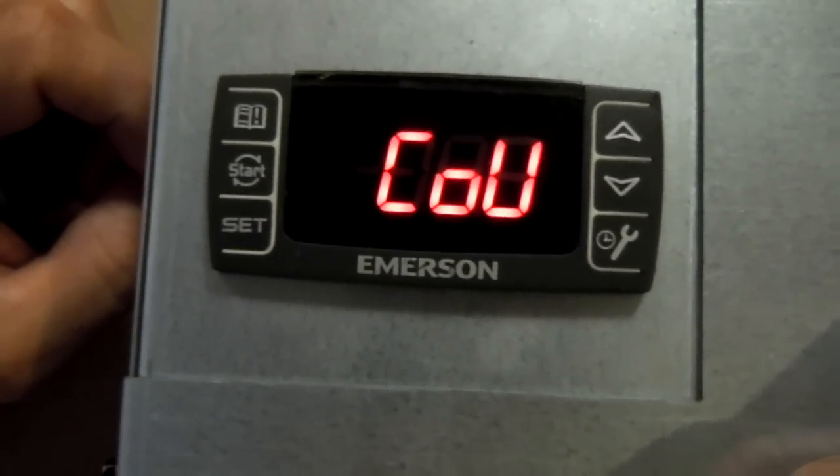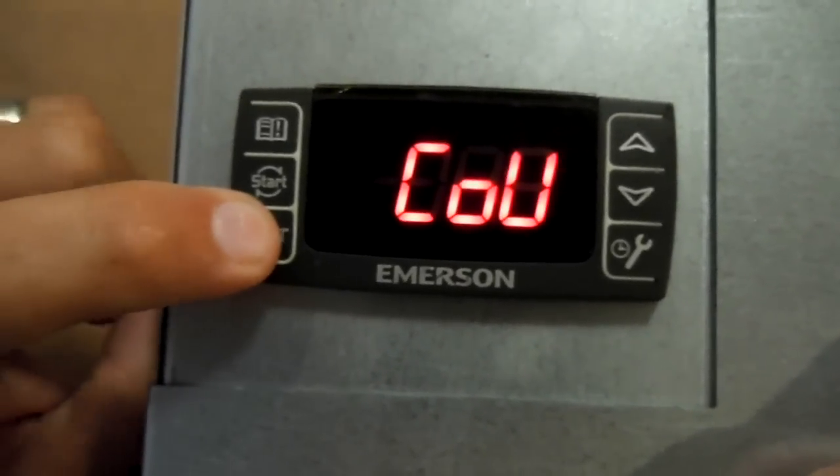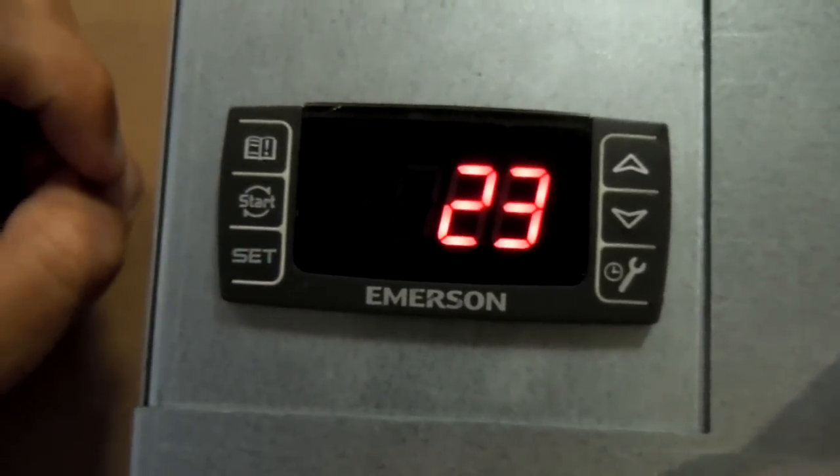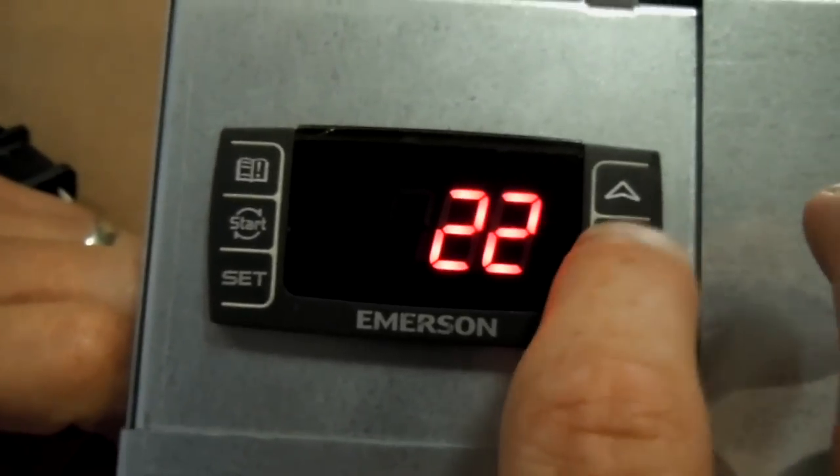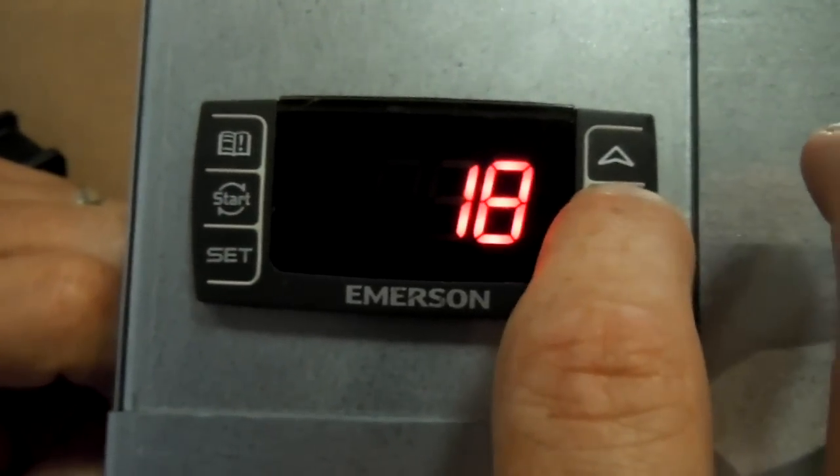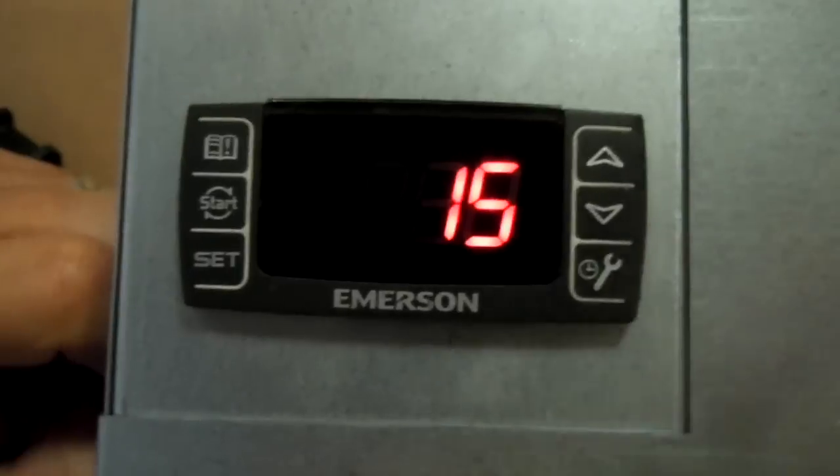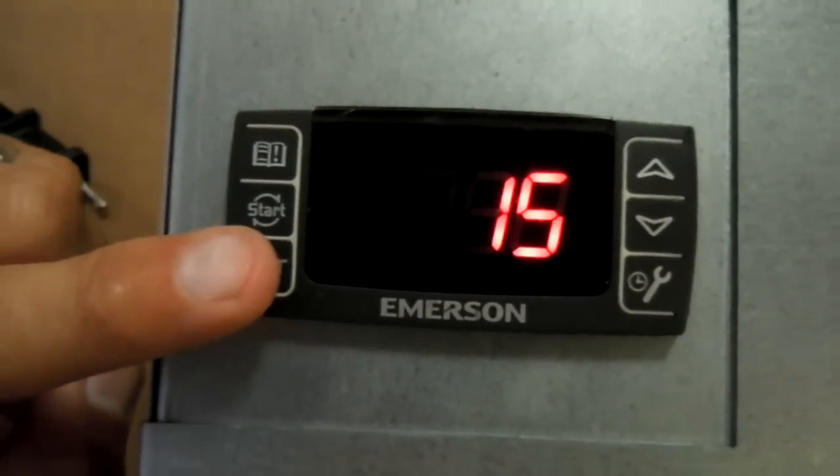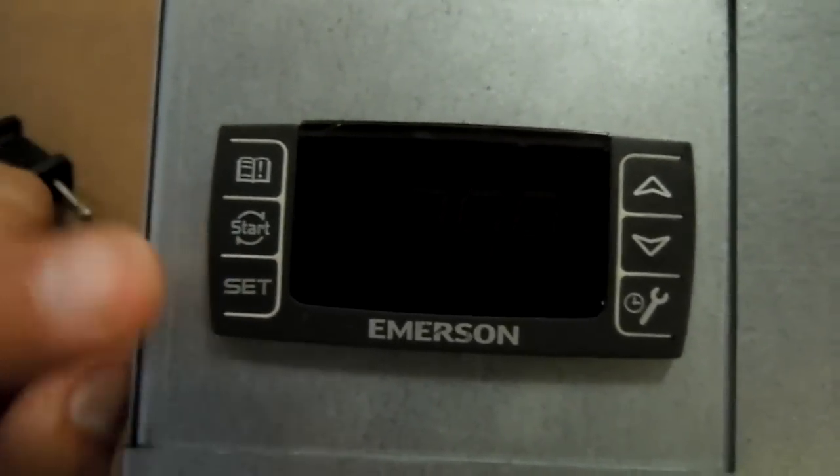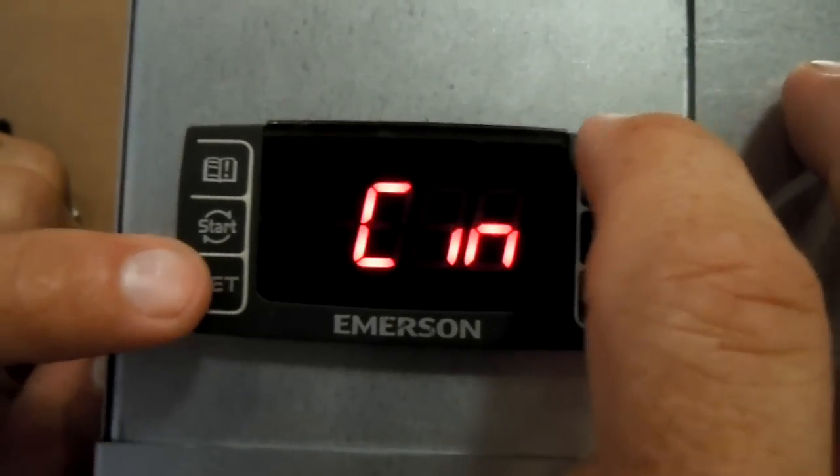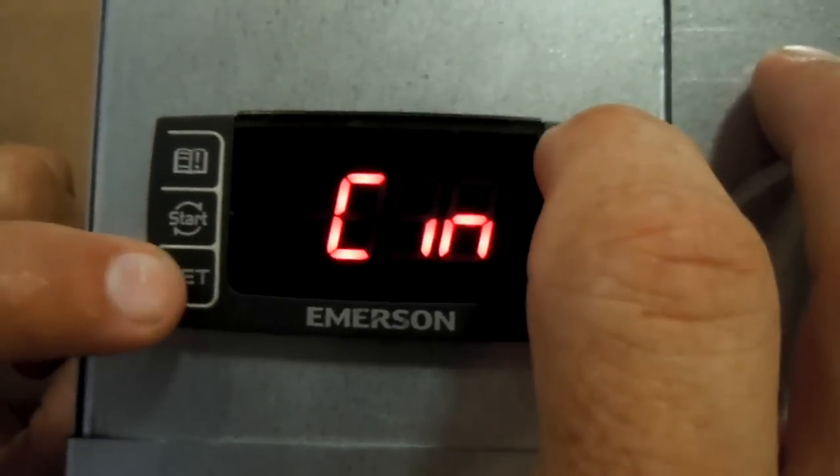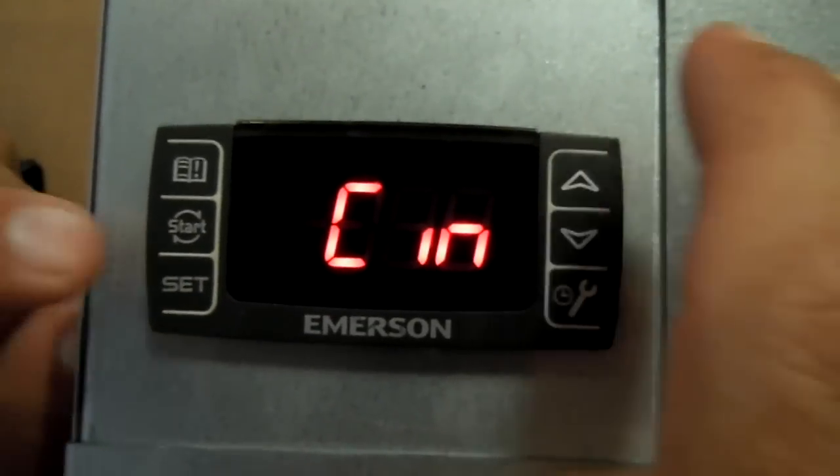Now to set up your cut out parameter, you hit set and then you can bump the pressure to wherever you want the cut out to be. And in this case, we'll put it at about 15 PSIG. So then you hit set to lock that in and hit set again. And there you go. And then to get out of the setup, hit set and the up arrow and there you have it.